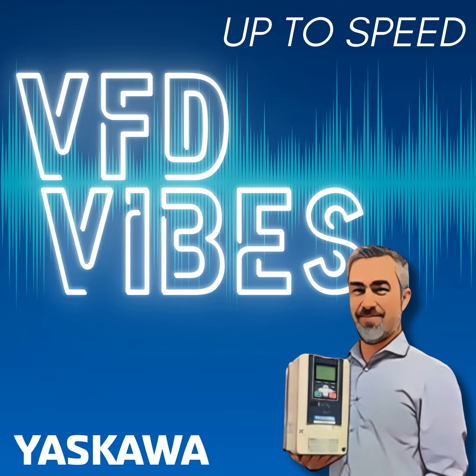Moving on to the next piece. I'm working through my project. I know a VFD is going to give me the best possible performance in terms of process control. And we've been able to use this first tool to figure out that the ROI is favorable. Do I have to worry about any impact on my power system? You bring up one of the few things that I don't consider a drawback, but it's something that needs to be considered before you purchase a VFD. And that is the effect of the VFD as a nonlinear load on your power system in your facility.